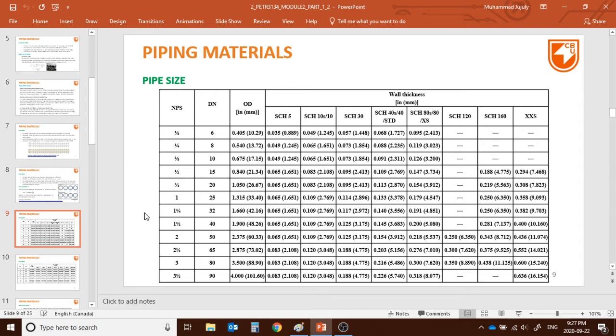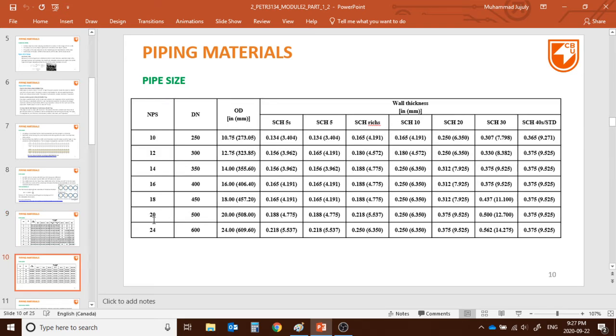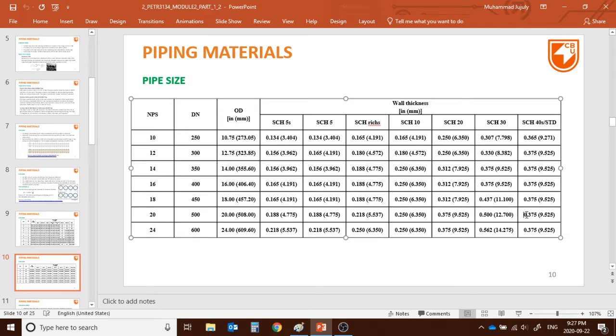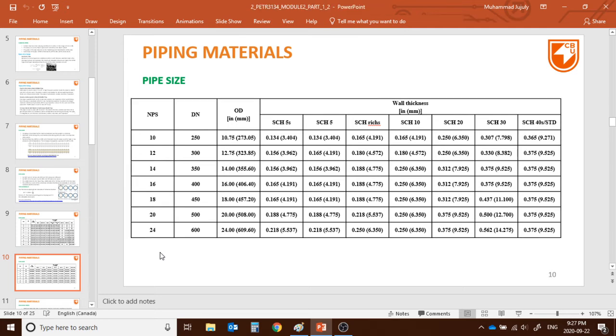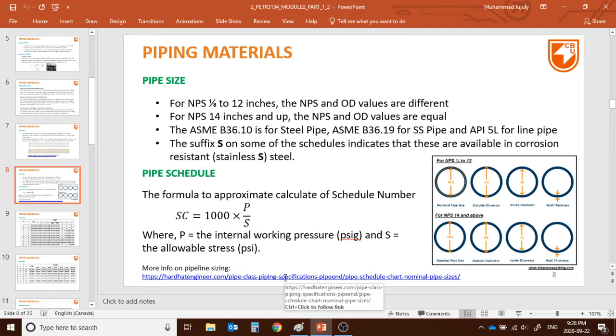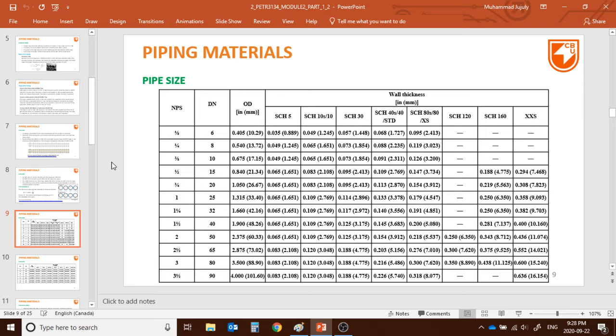For instance, NPS 20 with schedule 40 means the wall thickness is 0.375 inch (9.525 mm) and the diameter is 20 inches. For NPS 10 with schedule 30, the outer diameter would be 10.75 inch and the thickness would be 0.307 inch. You can find the full table online to get the whole list.